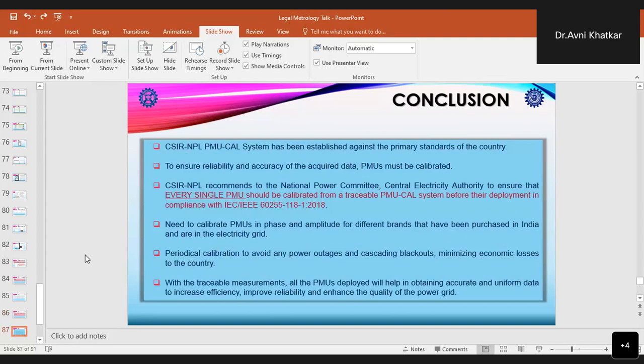Also, the CSIR NPL's PMU calibration system is established against the primary standards of the country, and in order to ensure reliability and accuracy of the acquired data, all the PMUs should be calibrated. CSIR NPL also recommends to the NPC that, in order to ensure this, every PMU should be calibrated from a traceable PMU calibration system before deployment, in compliance with the IEEE standard. And we need to calibrate PMUs in phase and amplitude from the different brands that are being purchased in India and are in the electricity grid.